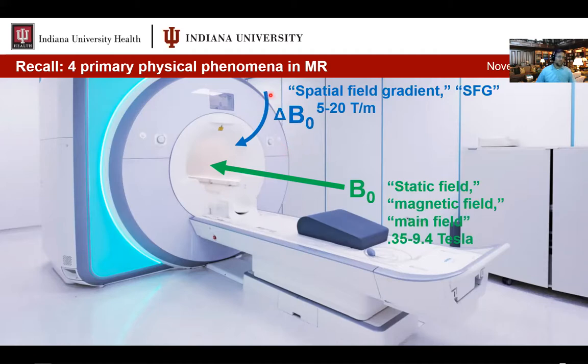Nonetheless, we need to be aware of these spatial field gradients. As we talked about in my first discussion, the magnitude of these gradients is highest near the edge of the bore, and it occurs in a donut-shaped area all the way around the bore. So remember, this is a three-dimensional magnet. It's a cylindrical magnetic field, and this spatial field gradient occurs at all points around the bore of the magnet.